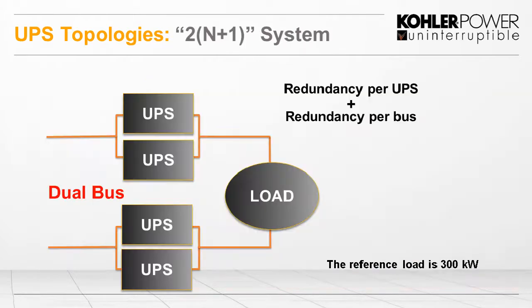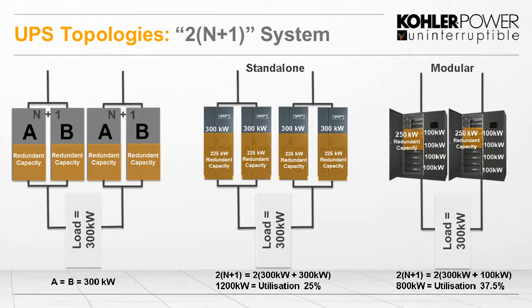Now, when we want to look at the ultimate redundancy, resilience and availability, we often get asked now for a 2N plus 1 system. This is where we have redundancy at the UPS and redundancy at the load on the bus. So again, we're looking at this 300 kilowatt reference load, and we'll produce this either with standalone units. In this case, we'd have to have two on each side. So an N plus 1 on each side of the load, which makes it the 2N plus 1, which is 1.2 megawatts, 1200 kilowatts of UPS, utilizing only 25% of it in normal running.